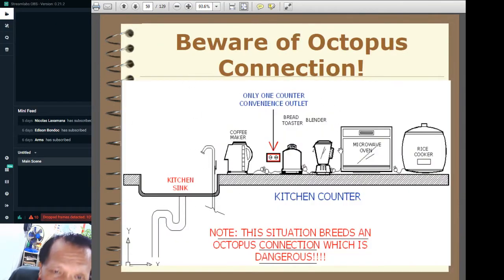Okay, here is a slide showing our kitchen sink, with so many appliances and only one outlet. We should refrain from having only one outlet in the kitchen counter that has so many appliances. According to the latest provision of the code, if your kitchen counter exceeds 2 feet, you must provide another outlet. So 2 outlets should be provided in excess of 600 mm or 2 feet. But the real reason is, of course, if you have so many appliances like a rice cooker, microwave oven, a mixer or osterizer, a bread toaster, coffee maker, and so on, and you have only one outlet, chances are they will not fit into your outlet.